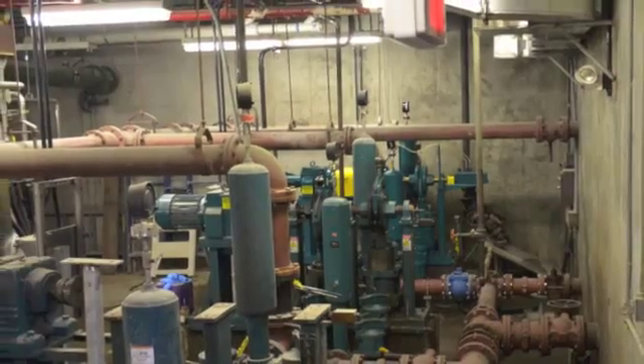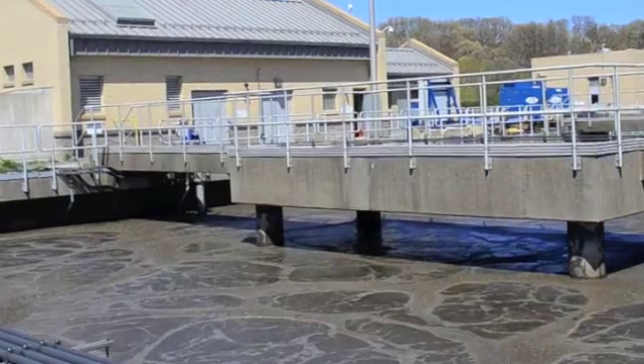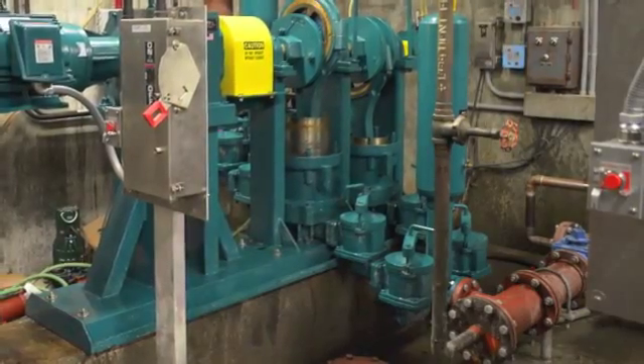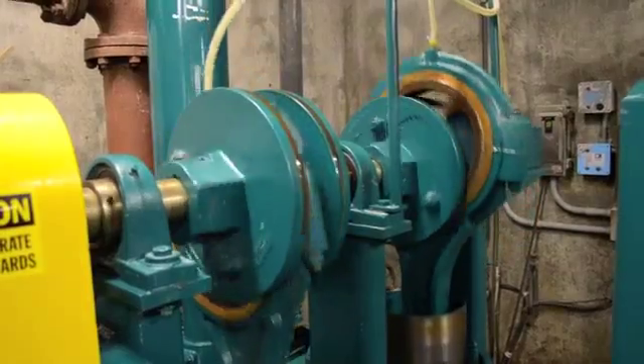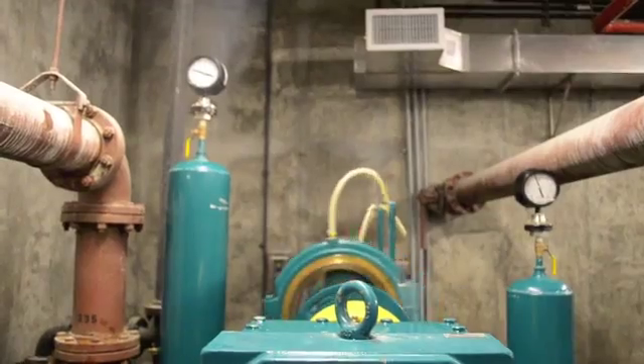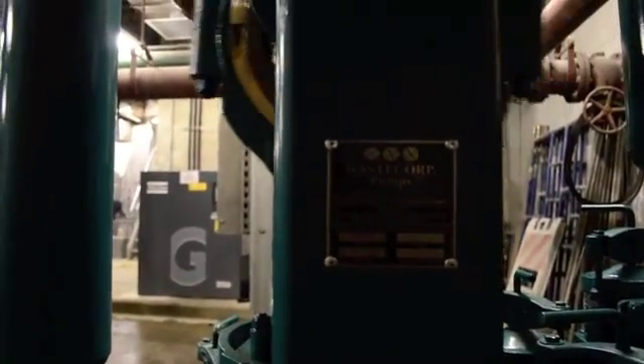Since the workload of these pumps is set to exceed 10 hours per day and the variation in grit, solids, and fluid consistency is expected to vary, the pumps are designed with a dual ball valve configuration to manage these punishing conditions. Suction and discharge gauges are also specified to more easily identify blockages in the line, which may ultimately prevent pump damage.